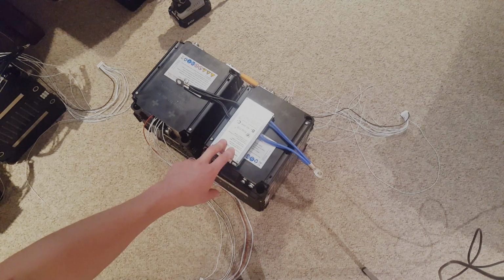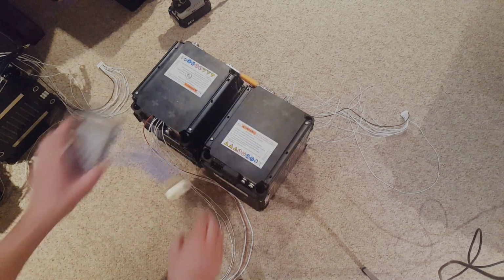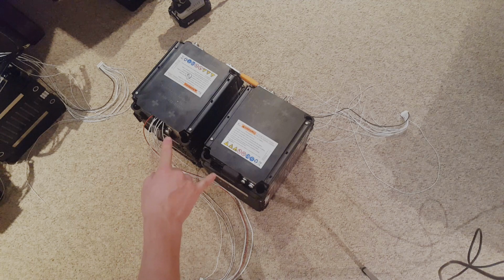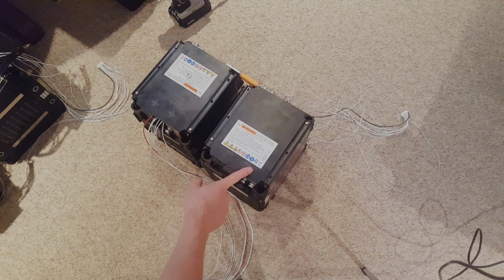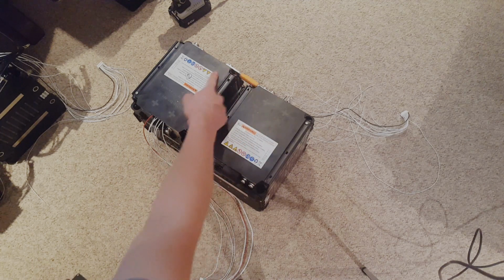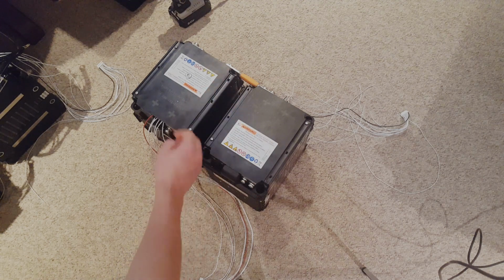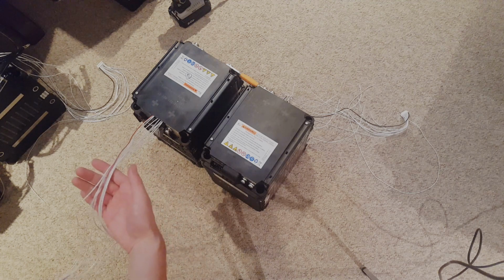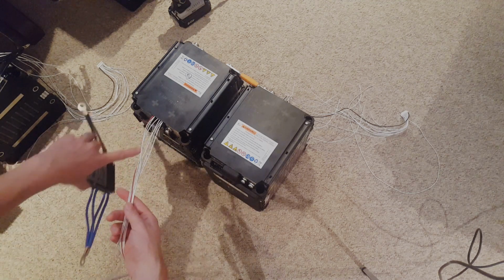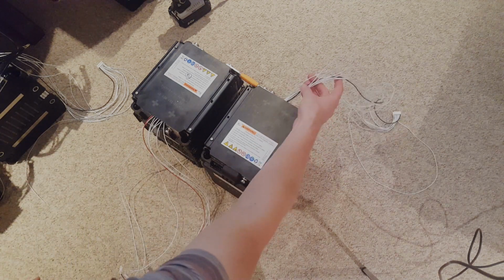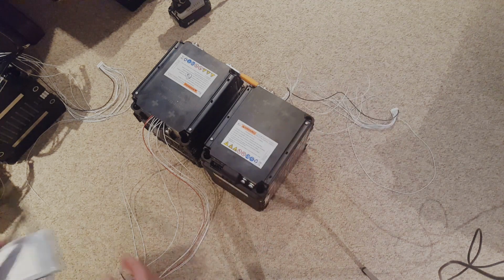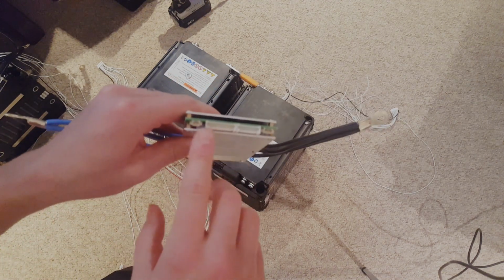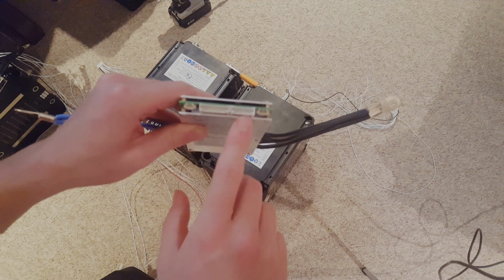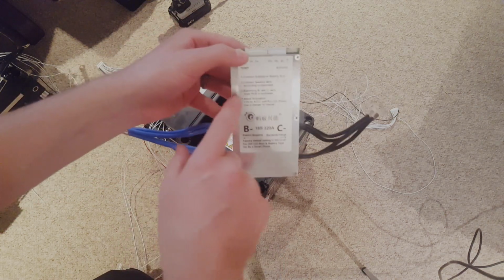Alright, I have all of the balance leads wired up for all of the batteries. Now we're ready to start getting our settings put into these. I have these wired in series already. This isn't how they're going to sit on the rack, but this is our main negative, and then it flows up here, and this is the negative on this side, and this is the main positive for the two in series. You can see the red wire here for main positive, and this is going to be for the main negative. You can see that black wire here, and these connectors are actually different sizes, so you can't mix those up, so that's cool.